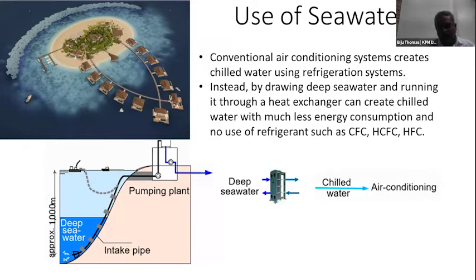The chilled water is then pumped into a heat exchanger where the primary circuit is the seawater, which comes in and is thrown out again. On the secondary circuit, we have our normal chilled water system used for air conditioning the premises. This is a very low energy consumption system, and the use of refrigerants like CFC, HFC, etc. is avoided.